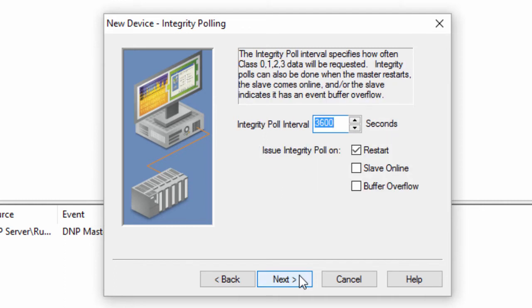Click Next to specify the integrity poll interval. We recommend this to be no more than once per hour. However, for most applications, very infrequent times of 8 to 24 hours or more is sufficient. Integrity polls can also be used on a master restart when the slave comes online or when the slave encounters an event buffer overflow.